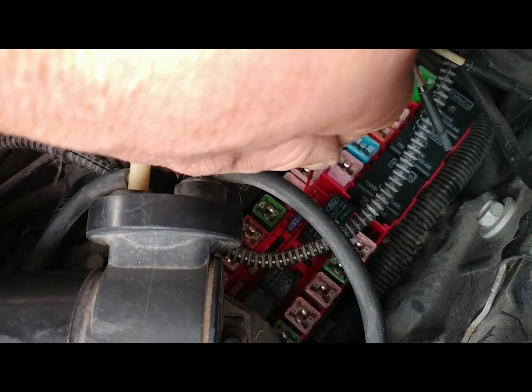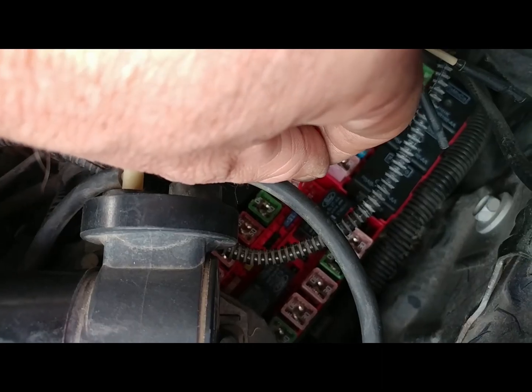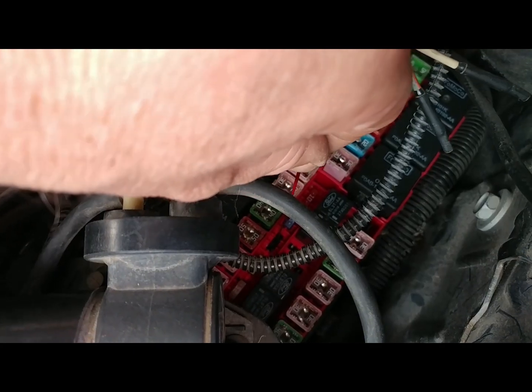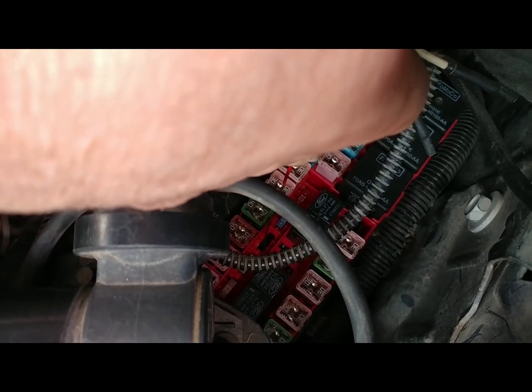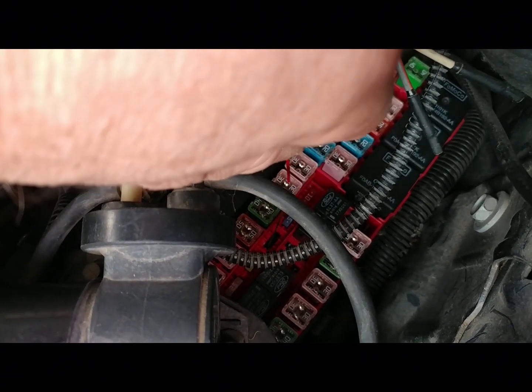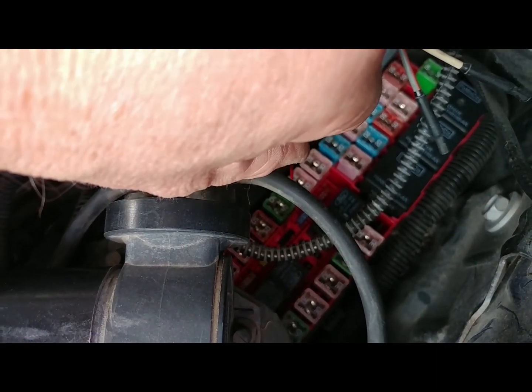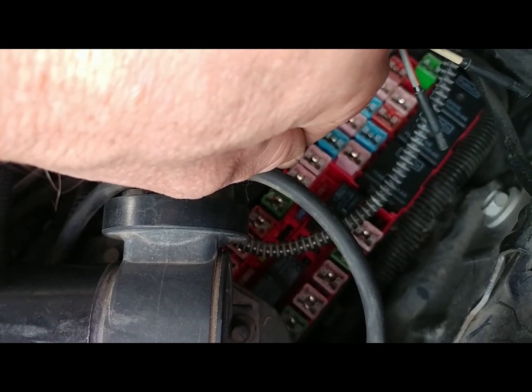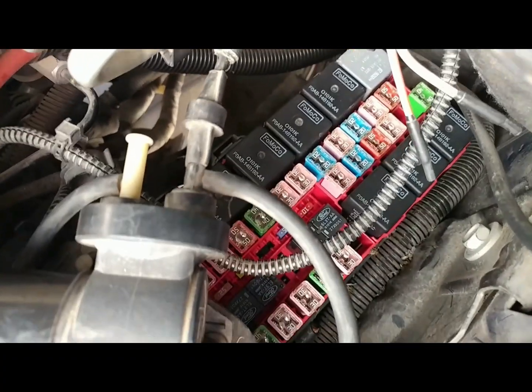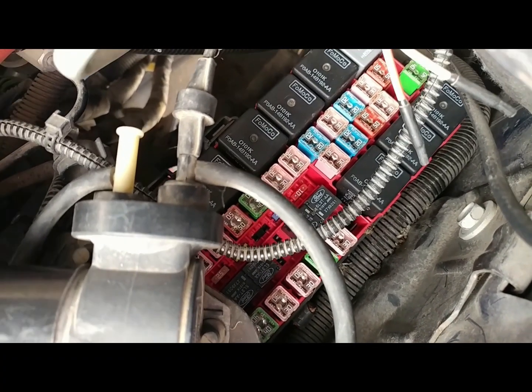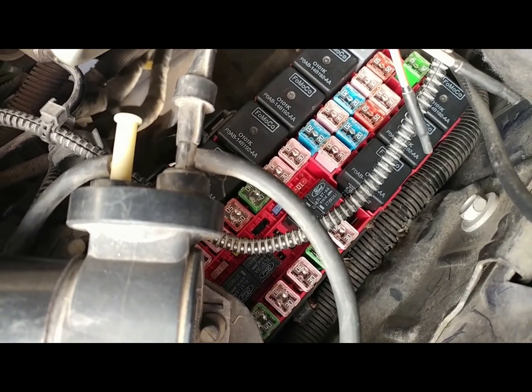Right now the file serves two purposes. I'm using it like a feeler gauge to judge how much spring is left in the contact in the fuse holder base. One side is rather loose and the other feels the way it should, it's got the spring in it. So I'm twisting a little bit with this file as I insert it to clean up the contact surface on the fuse holder base. But we're going to have another issue, and I'm going to show you how to deal with it.